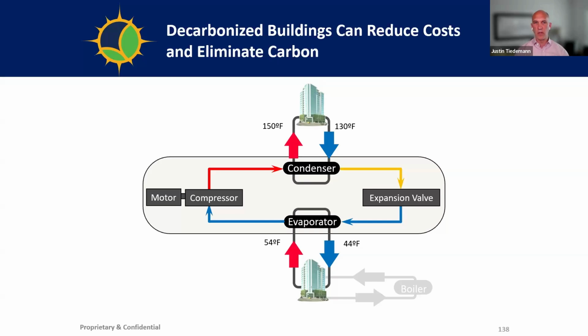So in this middle oval, you want to install heat pumps. You're going to take 80-degree condenser water and bump it up to 150 degrees for your heating hot water. It's really important to do the energy efficiency work to reduce the heat load and meet those building loads with lower heating hot water temperature.